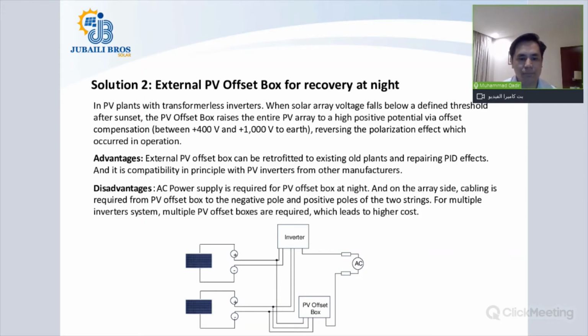What is the advantage of this solution? The external PV offset box can be retrofitted to existing old plants and repair PID effects. Normally one PV offset box is adaptable to many different manufacturers, so you will get the flexibility of using one single brand with multiple inverters. The disadvantage of the PV offset box is that with each inverter you will need a PV offset box, and you will need to cable the PV offset box to each string on the DC side. If you have multiple inverters in your PV plant, you will need multiple PV offset boxes, and you will be doing a lot of cabling.